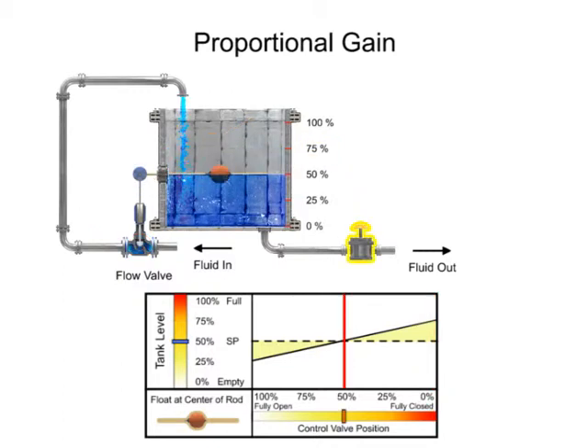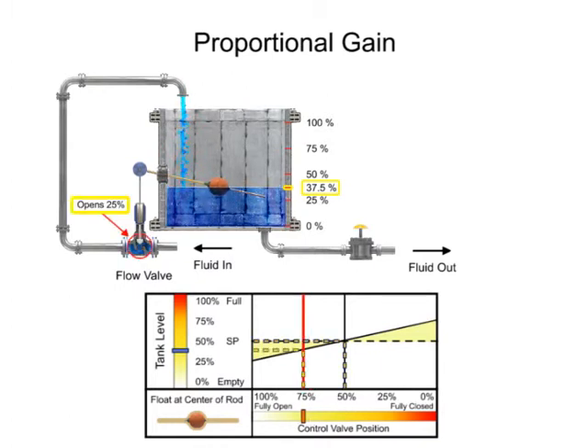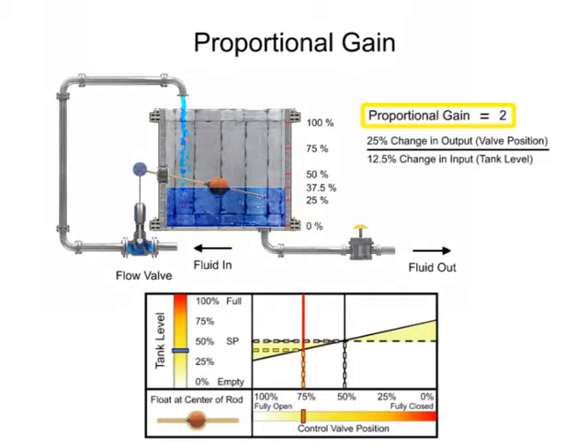Opening the drain valve increases the load demand which causes the tank level to drop by 12.5% or 37.5% full. The float drops and the valve opens 25% which allows more fluid flow to enter the tank. A gain of 2 is demonstrated in this mechanism since the 12.5% change of tank level resulted in a 25% change of valve position.